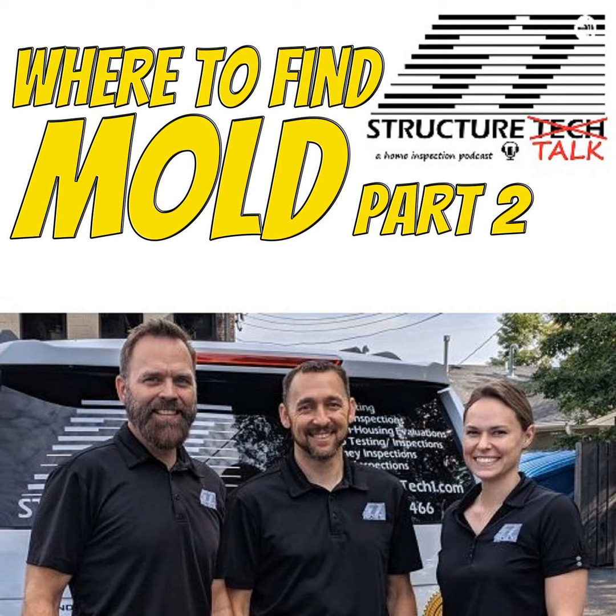So periodically look at these vent covers and check for obvious signs of mold growth. We don't see that problem with old metal vent covers as much. Occasionally I'll see mold on an HVAC supply, and one cause can be an oversized air conditioner. It cools the space and shuts off before it runs long enough to really remove the humidity. Some people think bigger is better, but part of the unit's job is removing humidity. If your air conditioner shuts down before the humidity is gone, that's when you'll see mold on the vent covers.